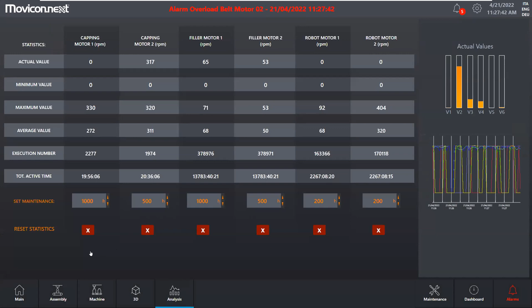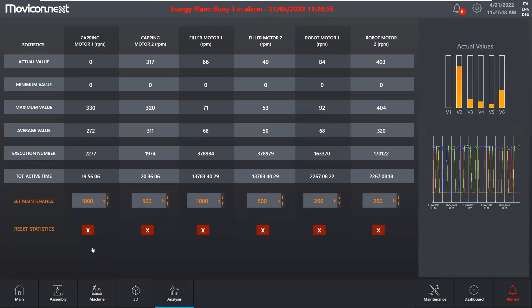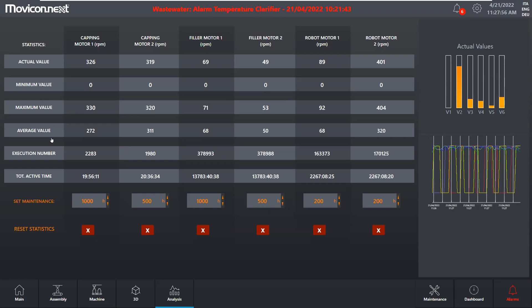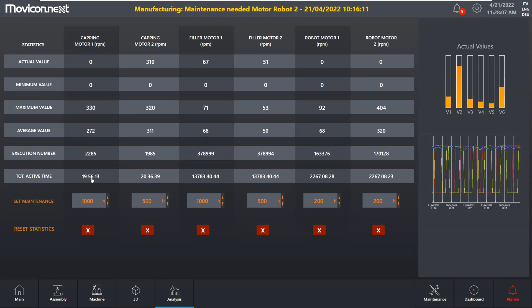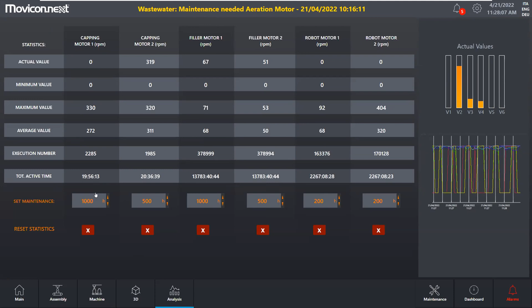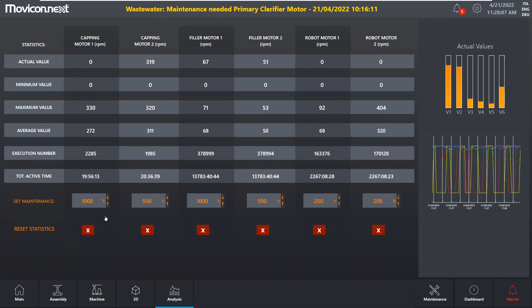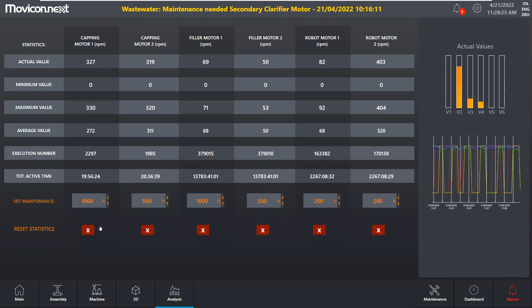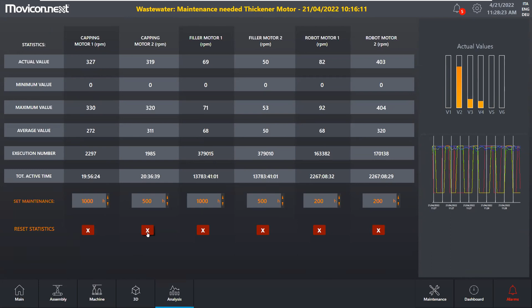Again, so all these can be found inside of the symbol library and the toolbox. The product has a statistics and analysis feature that you can enable on each tag. This basically allows Movicon, if enabled, to track different values on individual tags. So you can track min, max, and average value for the day, the week, the month, the year. You can do lifetime values. So let's say if you had a motor that was running, anytime it's running, Movicon would keep track of the total time on. So you can maybe set some alarms or alerts to notify maintenance staff that something needs to be checked or monitored or attended to, and then they can actually reset these values using the built-in commands.